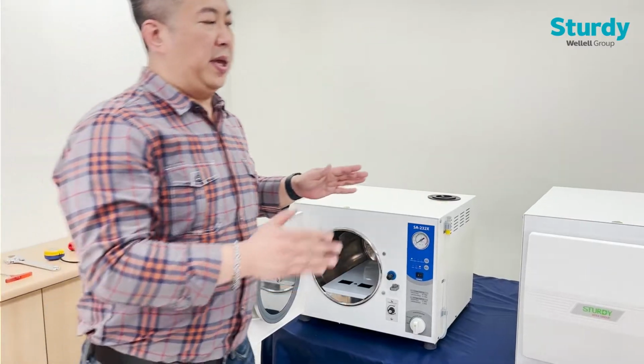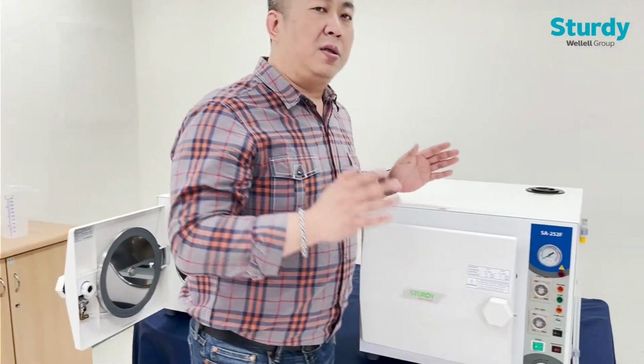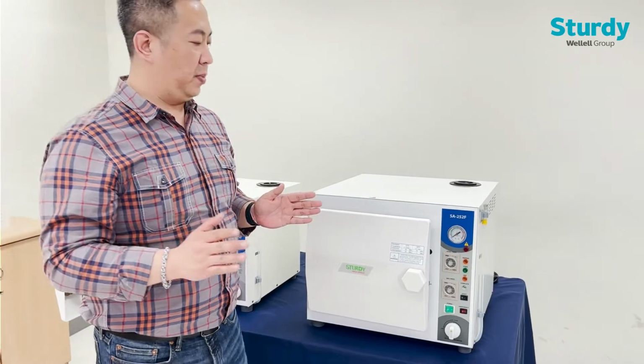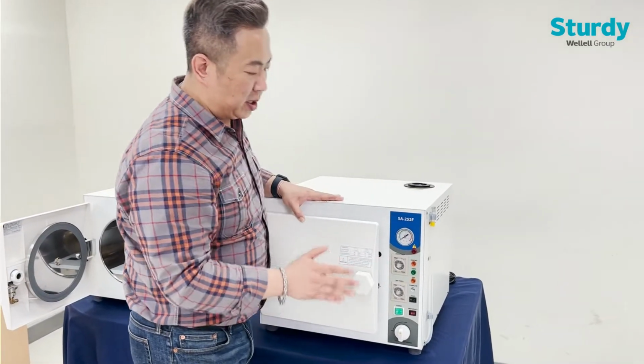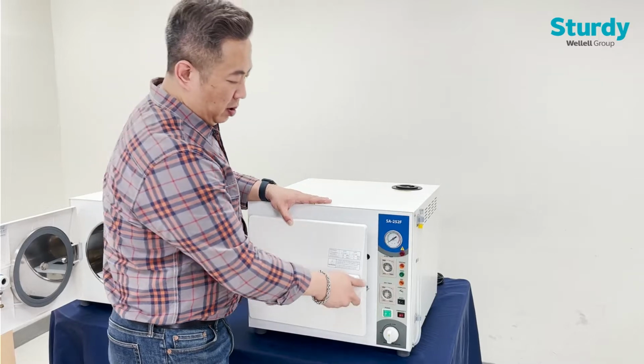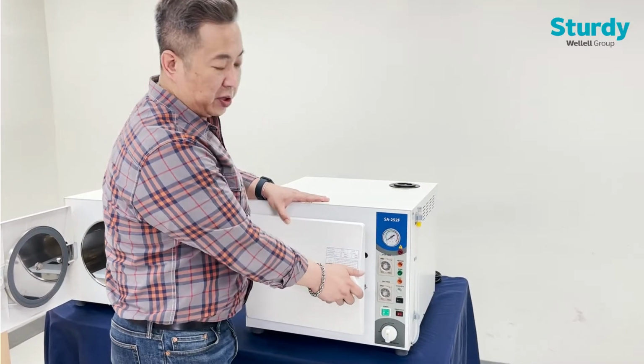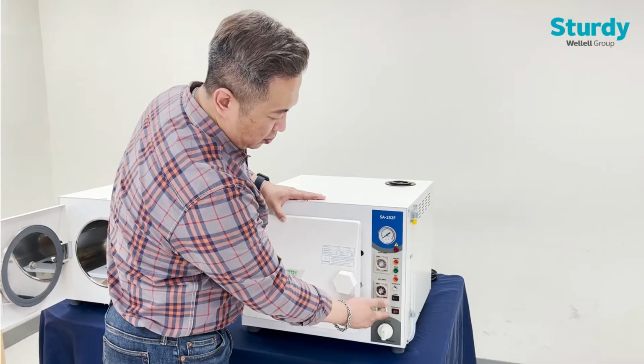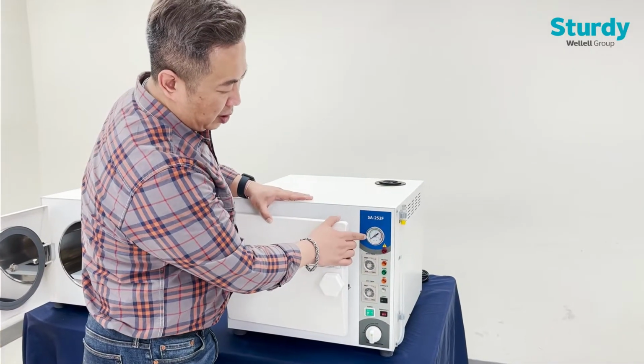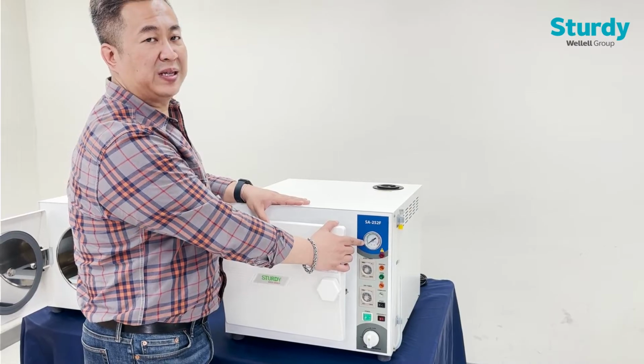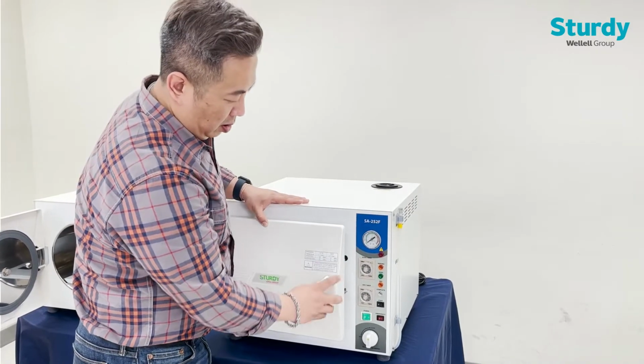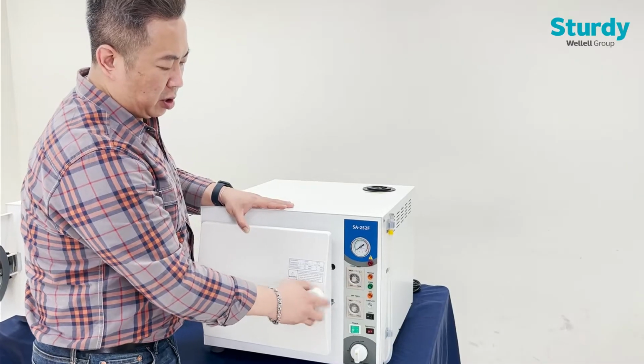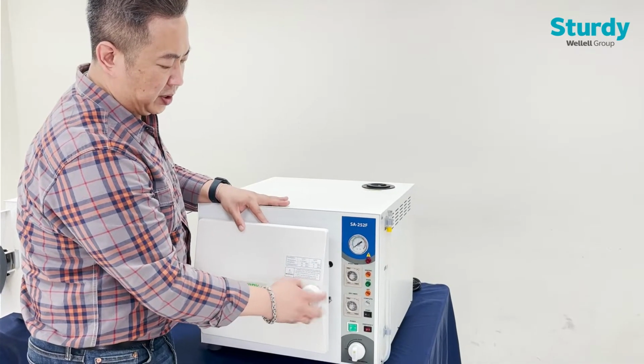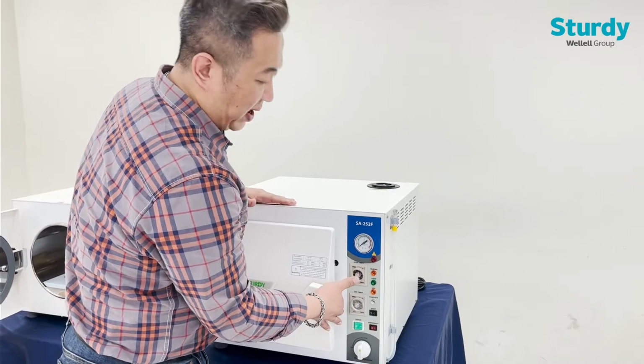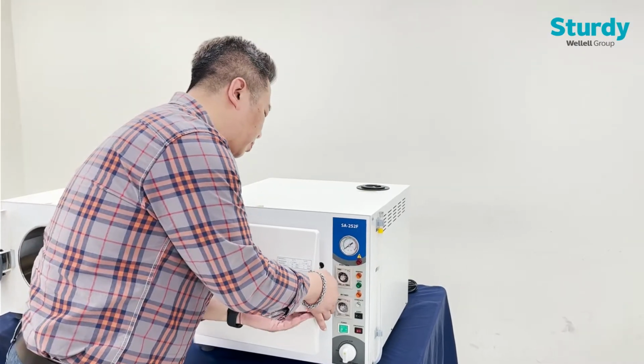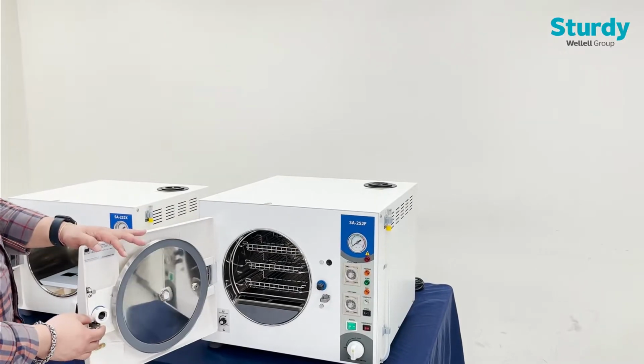Now, moving on to the SA252F, the process is identical. The difference is on the control panel itself. Again, before opening up the chamber door, the machine is switched on. We have to ensure that the internal chamber pressure is sitting at 0. Turn the handle anti-clockwise, fully loosen the handle, lift up the safety latch, and then open up the chamber doors.